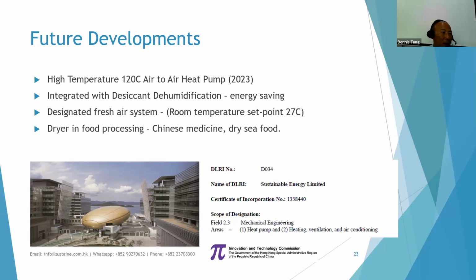And with a designated fresh air system with very low dew point achieved from the desiccant unit, our room temperature set point can be set at 27 degrees Celsius, which is very comfortable. And with very low humidity, this temperature will be very comfortable, and much energy can be saved if the temperature set point inside a building is set at 27 degrees Celsius.